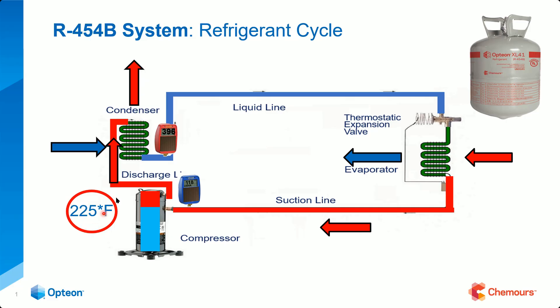Notice I've got 225 here. For those of you that have seen my videos, I've been saying it for years — 225, stay alive. We never want that discharge line temperature to be higher than 225 degrees, six inches out on the discharge line. I've had people see me in an airport and holler '225, stay alive' — kind of funny.